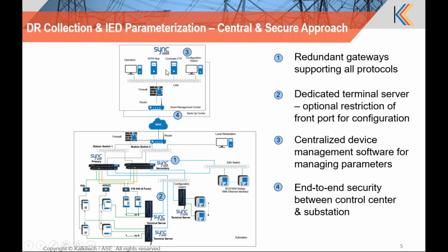Then there is end-to-end security. We have a dedicated tunnel between multiple substations and the control center using the TLS 1.2 encryption mechanism, and we support all role-based access. Different user groups can be created based upon the roles assigned to the group, and under the user group, multiple users can be created.